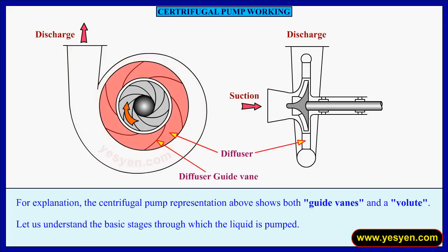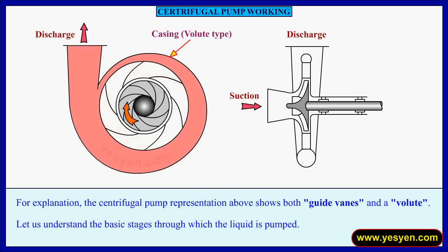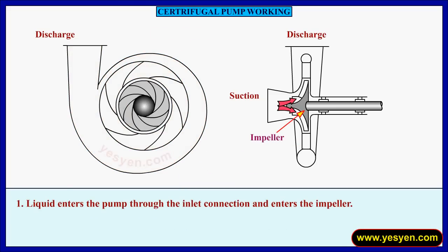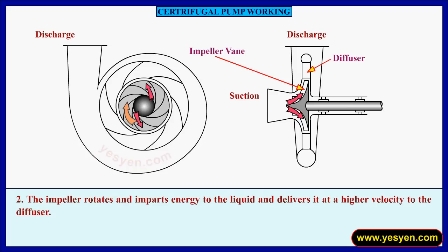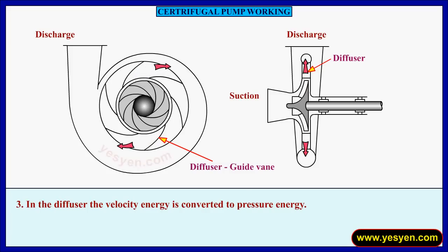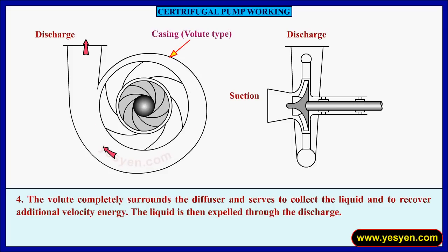The centrifugal pump representation shows both the guide vanes and the volute. Liquid enters the pump through the inlet connection and enters the impeller. The impeller rotates and imparts energy to the liquid, delivering it at a higher velocity to the diffuser. The vanes of the diffuser are tangential to the impeller. In the diffuser, the velocity energy is converted to pressure energy. The volute completely surrounds the diffuser and serves to collect the liquid and recover additional velocity energy. The liquid is then expelled through the discharge.